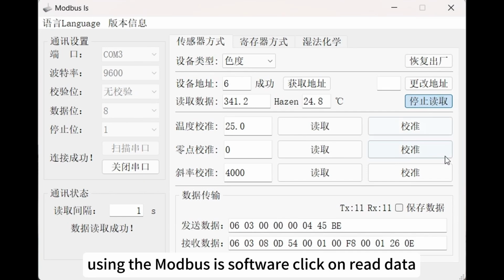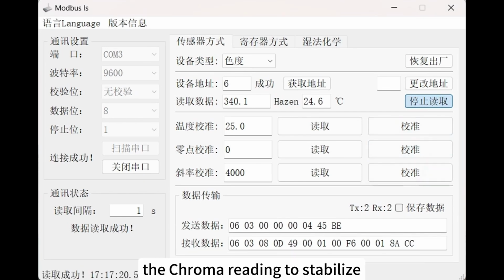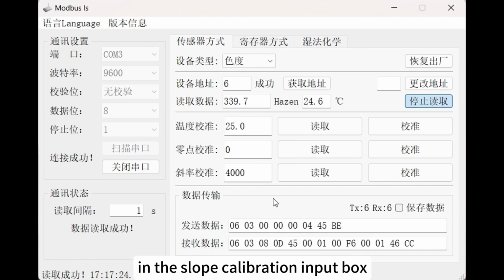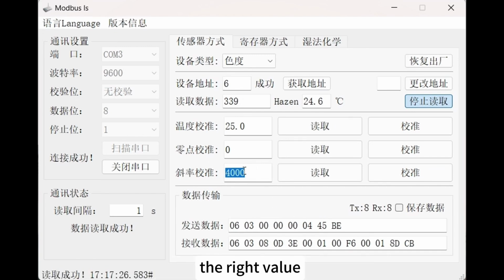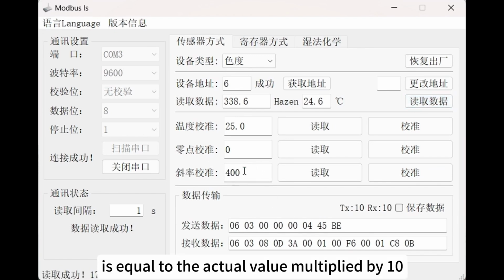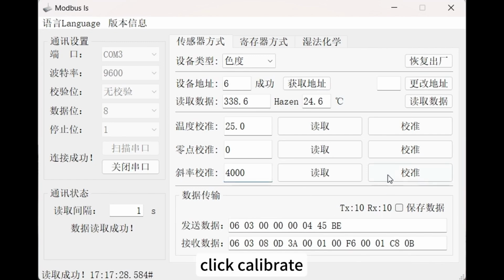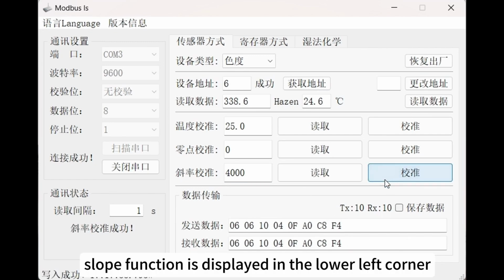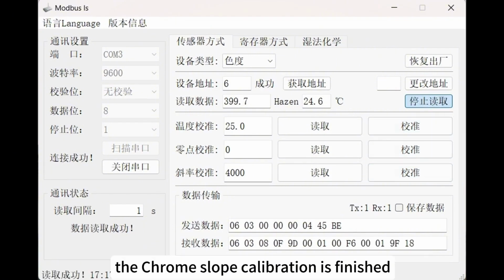Click on Read Data. Allow the chroma reading to stabilize. Enter the right value in the slope calibration input box. The right value is equal to the actual value multiplied by 10. Click Calibrate. The slope calibration success is displayed in the lower left corner. Click Read Data. The chroma slope calibration is finished.